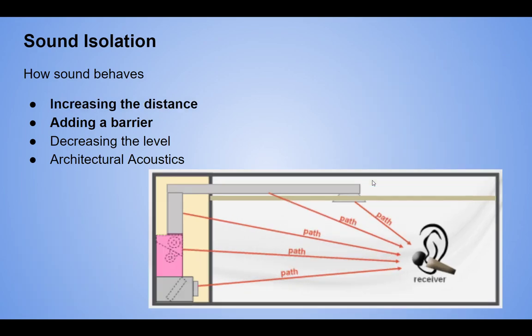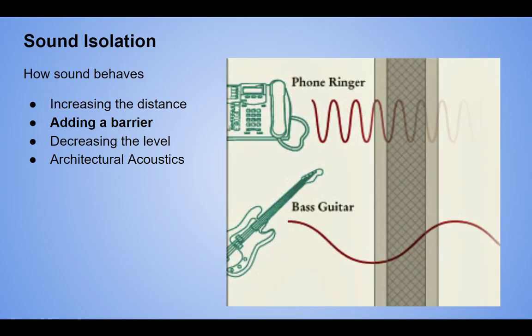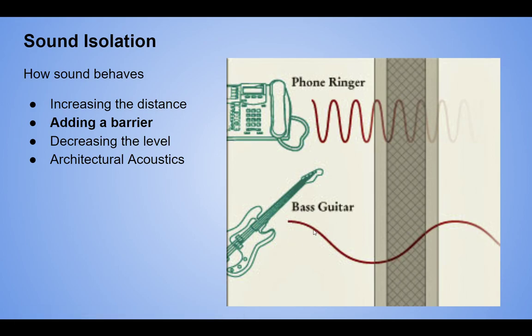Increasing distance and adding a barrier are the most efficient ways. When adding a barrier, know what you're trying to block. A single number descriptor like STC is kind of misleading — this wall might be STC 40 but you can see in the illustration the sound is getting through at certain frequencies. It's not that the bass guitar is louder, it's that it's a different frequency and that wall basically doesn't see it — it's like it's not there.